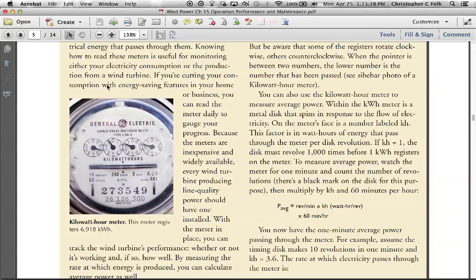So it's showing here that this one has 6,918 kilowatt hours on it. The reason I bring this up is because not all meters have the capability of turning backwards. Some power companies will require a second meter to be installed, one used for revenue and one for consumption. In that case, we may have two separate meters, or more preferable would be a meter that could spin both ways.